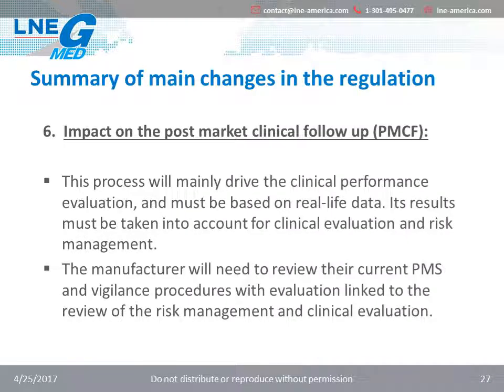To continue with the main changes in the regulation, the sixth point is impact on the post-market clinical follow-up, PMCF. This process will mainly drive the clinical performance evaluation and must be based on real-life data. Its results must be taken into account for clinical evaluation and risk management. The manufacturer will need to review their current post-market surveillance and vigilance procedures with evaluation linked to the review of the risk management and clinical evaluation.